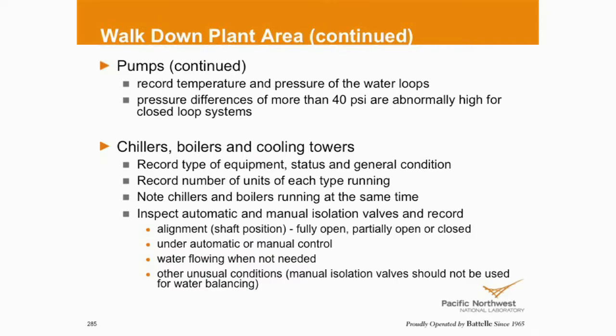Pressure differences of more than 40 psi are abnormally high for closed loop systems. We talked about 10 to 20, so yeah. Boy, I hope nobody has differential pressure differences between what's being supplied and returned that high, especially at the end of your loops. Again, look at your chillers, your boilers, your towers. How many are running? Are they running part loaded? Are they running for the load? Are they running unloaded? Are they short cycling like we talked about earlier today?